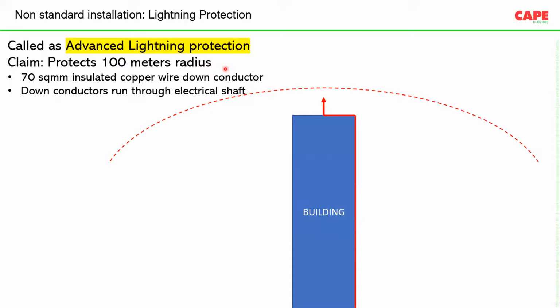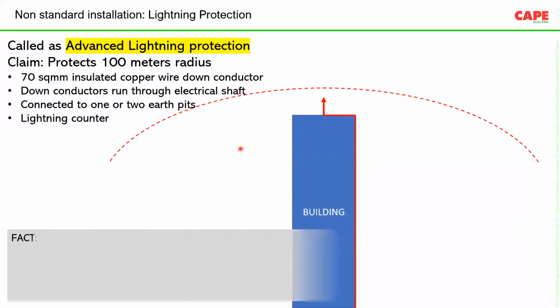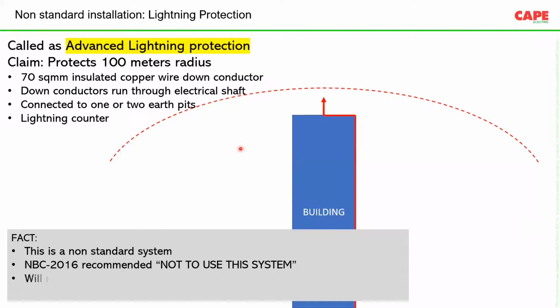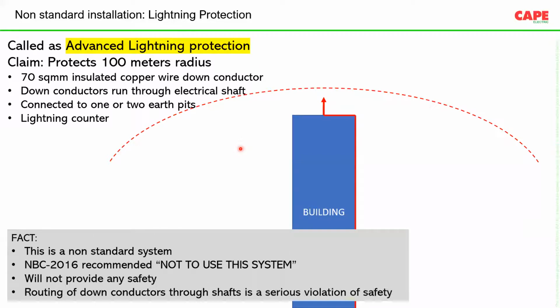People say, I protect not only me, I protect all my neighbors. And the dangerous part is not only this particular rod at the top of the building, but the routing of the down conductor is much more dangerous. Most of the time, there is only one down conductor routed through the electrical shaft. All of you know very well that this system is not recommended in the National Building Code, and this shall not be used in medical locations.